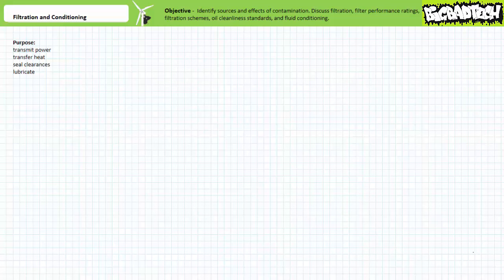These standards dictate permissible levels of contamination, filtration levels, maintenance schedule, and any special purpose conditioning needs. A contaminant is anything unwanted introduced to a system. Contaminants include, but are not limited to, dust, dirt, metal shavings, and shredded pieces of decaying gaskets or O-rings. Even oil itself degrades over time, and abused and damaged oil can be considered a contaminant to the system.